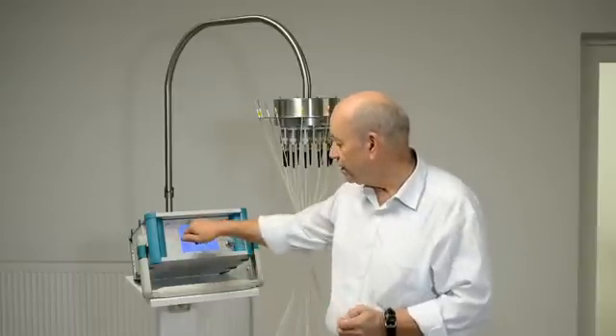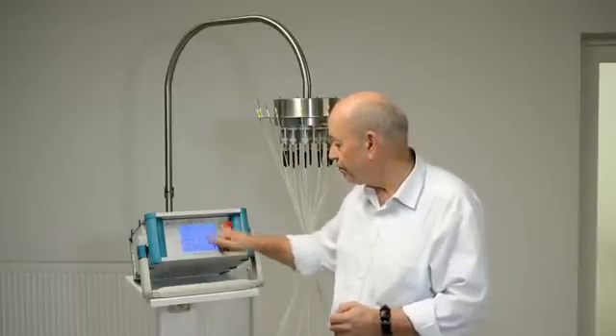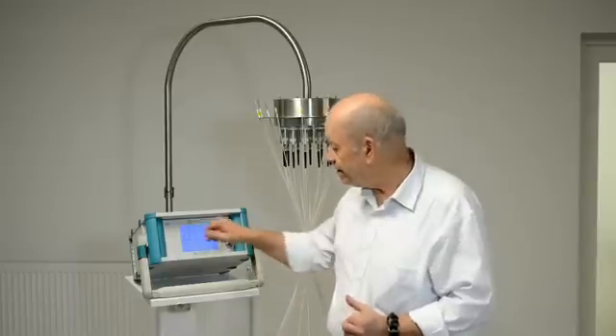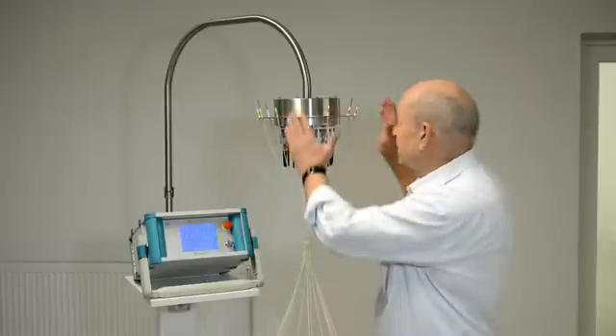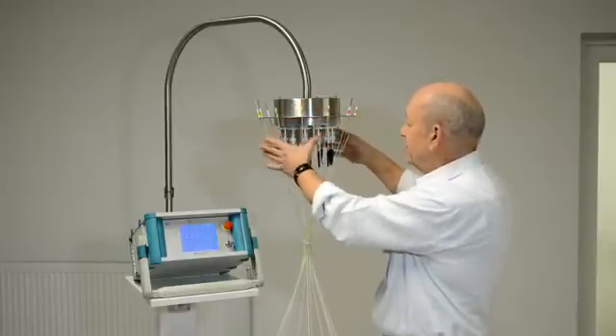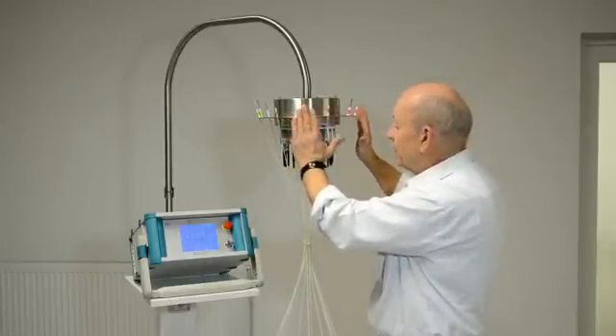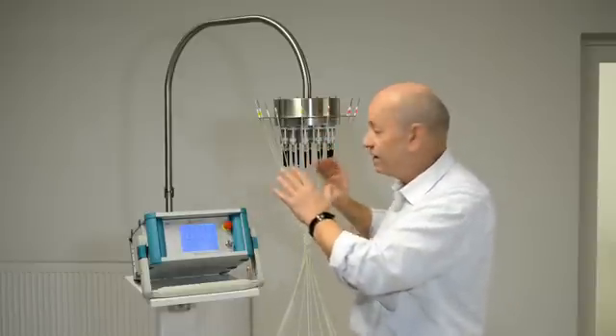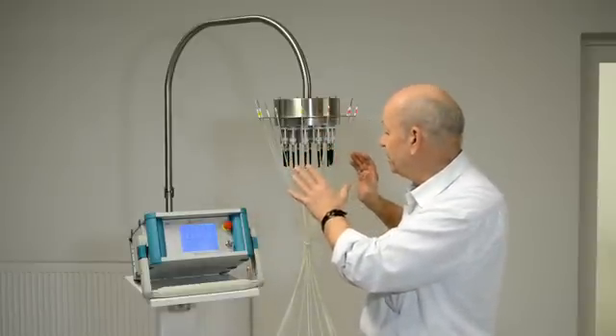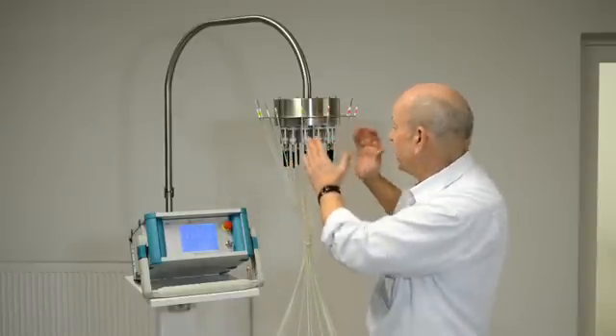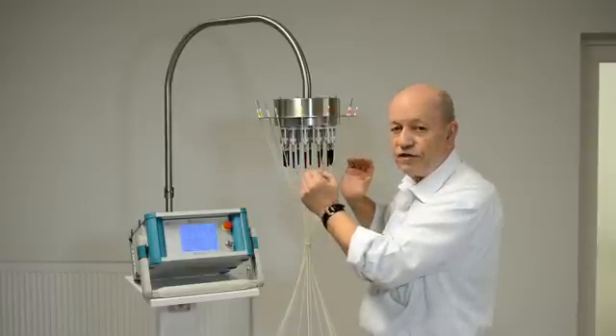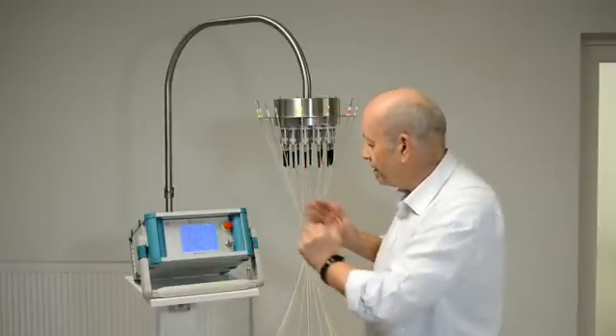The device is divided into two parts: we have the housing where the electronics is inside, and the laser modules are not in the device—they are inserted in a specific metal head which guarantees good cooling of the modules for long life of the laser diodes.